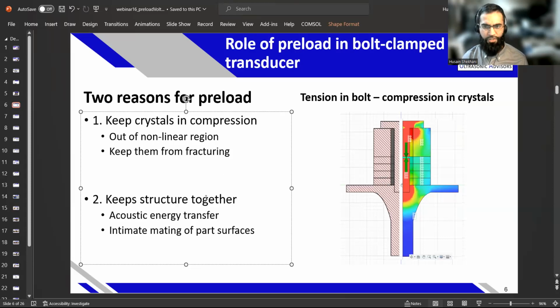But wait, we could just use glue and glue everything together. Why do we always use this bolt? Well, the bolt is used to keep the crystals in compression. That's one. The epoxy will not keep them in compression to the extent that you need for power ultrasonic transducers. This is why all power ultrasonic transducers have preload, because you will not be able to excite them with enough amplitude if you do not apply a compressive preload. That's kind of the bottom line.